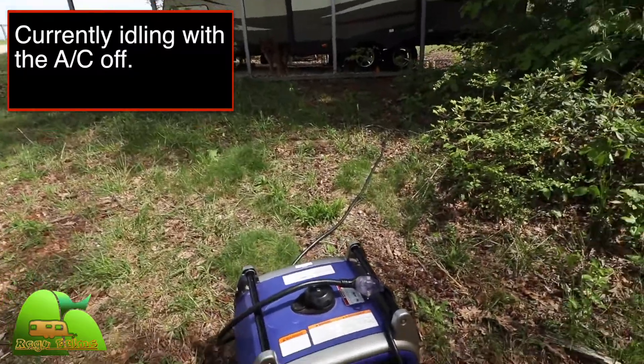My son's inside and he's going to start it up on my signal. You'll see that the generator showed about half of the overload light for only a half second or a second, and then it picked up running. Ambient temperature today is about 80°F. I'm going to give him the signal and we'll let you see what's happening with the generator. All righty, go ahead.